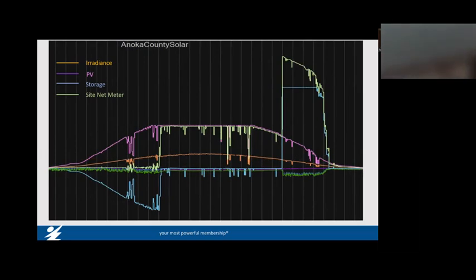Now the next day, we come in and those batteries are empty. One thing I'll mention is those are lithium-ion iron batteries. They don't like to be completely empty, and they don't like to be completely full. The ideal resting state of charge for these batteries is 30%. We've contracted with Nextera to keep them at a resting state of charge of 50%—not quite as good as 30, but still pretty good. Anything above a 50% state of charge, you start losing more life in the batteries.